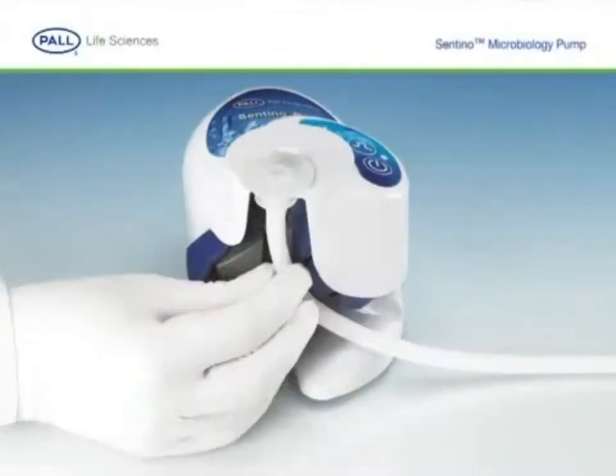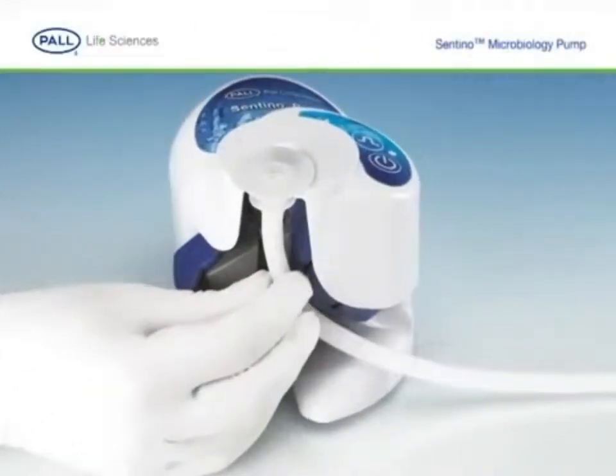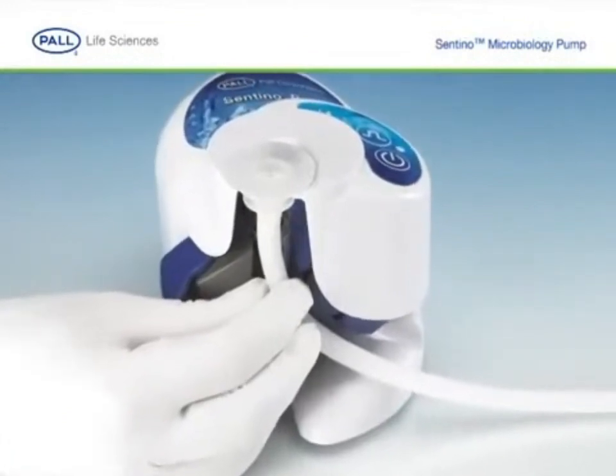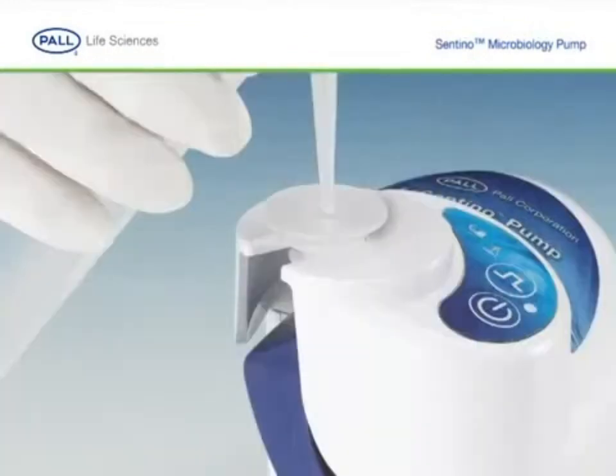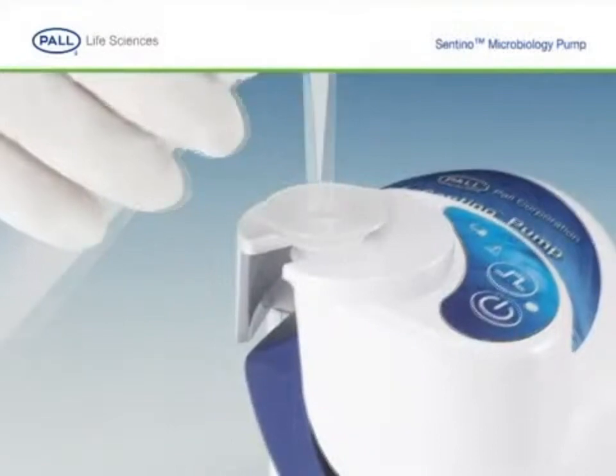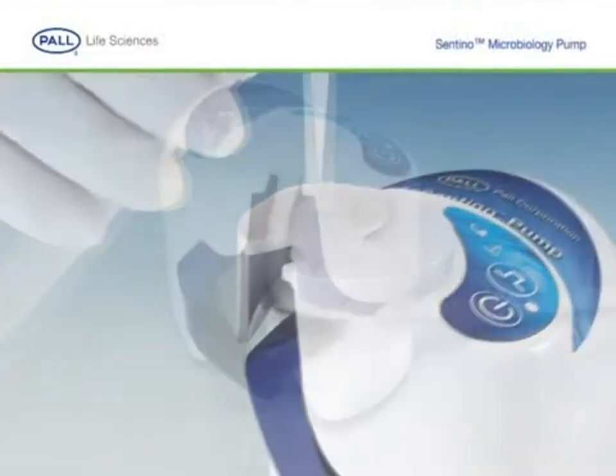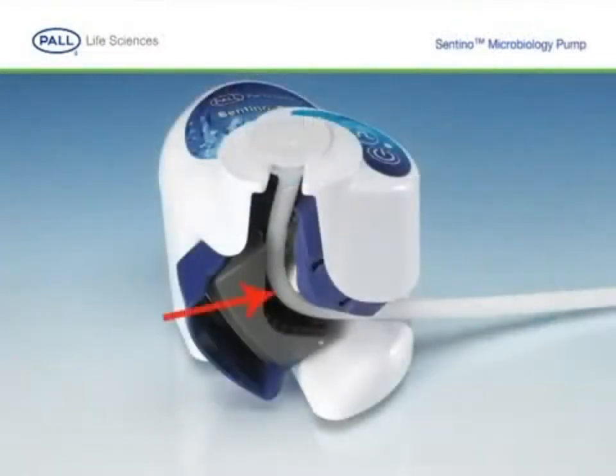Change the fluid path in the Sentino pump at least once a week. For optimal contamination control, replace it daily. Upon initial installation or at the end of a filtration series, rinse the fluid path with 70% IPA for 5 seconds. Pump residual alcohol through the tube and open the pump head loading door to relieve the tubing of any pinching from the rollers when not in use.